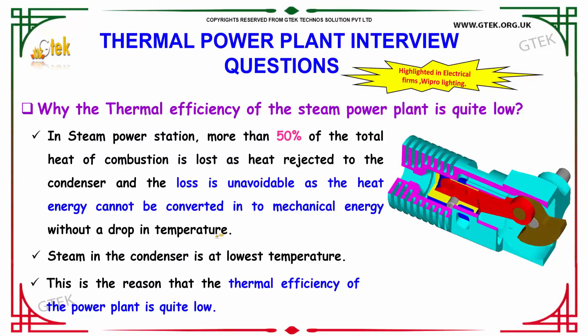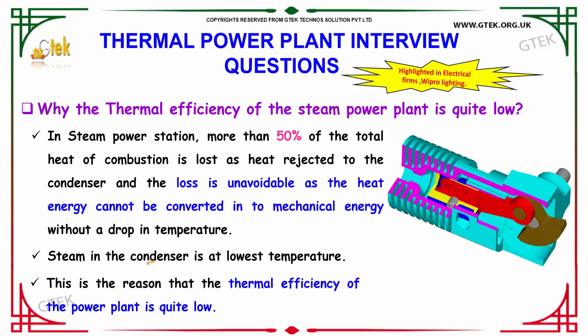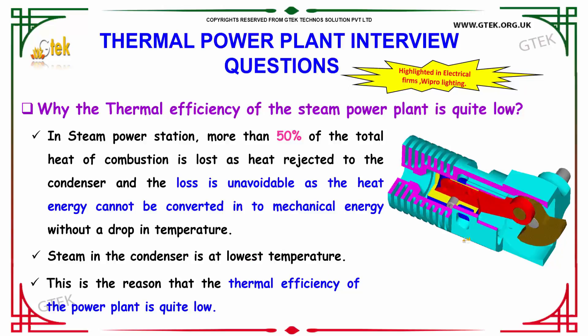We will move to the next question: why is the thermal efficiency of the steam power plant quite low? In terms of the steam power station, more than 50% of the total heat of combustion is lost as the heat rejected to the condenser, and this loss is unavoidable as heat energy cannot be converted into mechanical energy without a drop in temperature. Additionally, steam in the condenser is at the lowest temperature. This is the reason the thermal efficiency of the power plant is quite low.